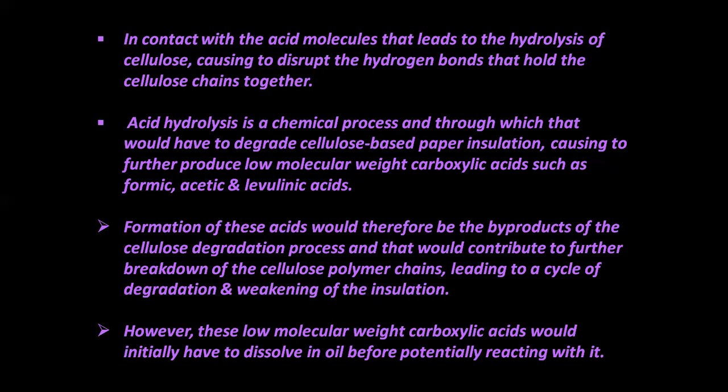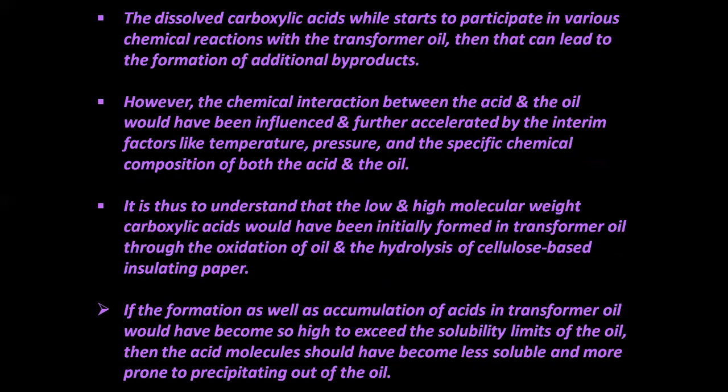However, these low molecular weight carboxylic acids would initially have to dissolve in oil before potentially reacting with it. When the dissolved carboxylic acids start to participate in various chemical reactions with the transformer oil, that can lead to the formation of additional byproducts.